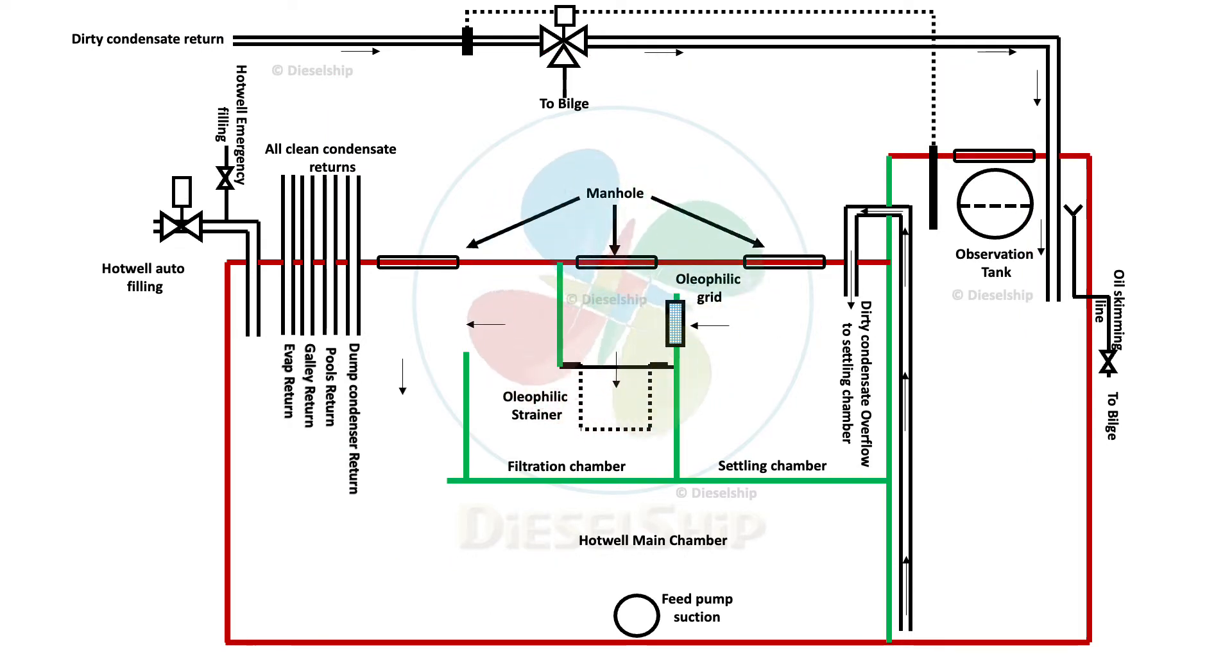All dirty condensates from different uses come and manifold into one line, the dirty condensate main. This line is installed with an oil sensor, which is of a capacitance type. If there is any oil present in this manifold, this oil sensor triggers the three-way valve to open to the bilge instead of going to the observation tank or the hot well.